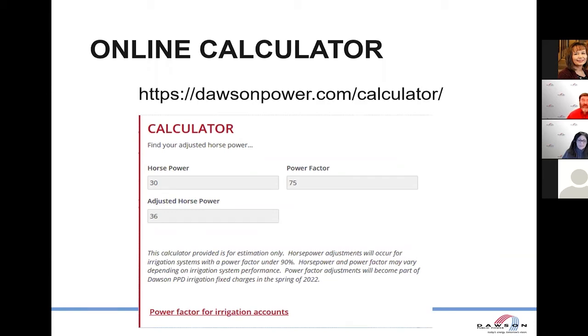Now, if you want to see how it's going to affect your horsepower on your bill, we have a handy tool we put on our website. So you can go to dawsonpower.com/calculator and use that to find your adjusted horsepower. And the example down below, this is a screenshot right from the calculator on the website. So you put in what your horsepower is off your bill or off your motor nameplate. You put in what your power factor is, that either your manufacturer gave you or you found off of this fall's bill. And we're going to show you the adjusted horsepower right there. So for this particular person with a 30 horse motor and a 75% power factor, their adjusted horsepower is 36 horsepower.